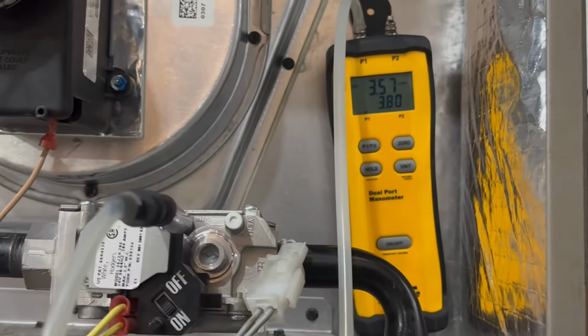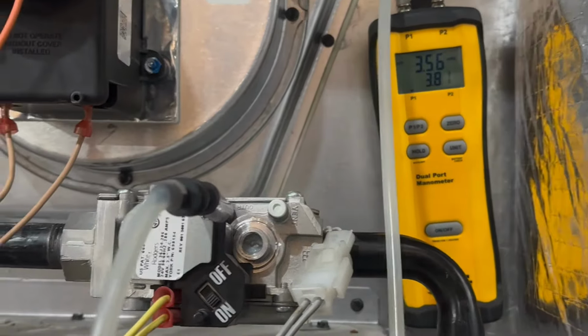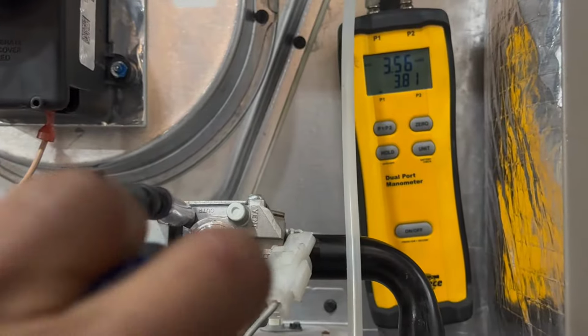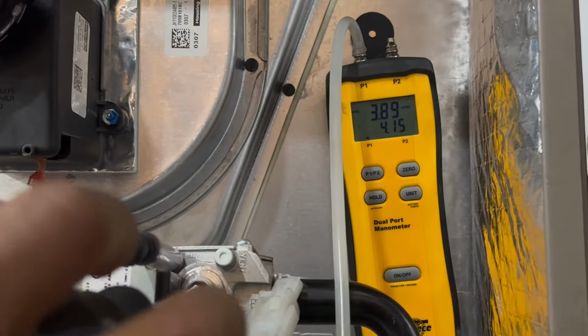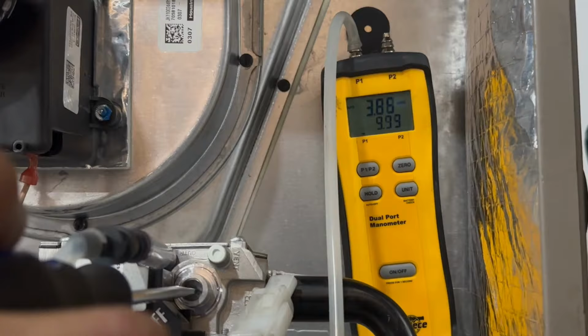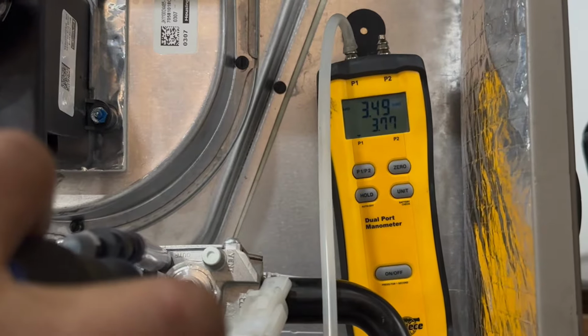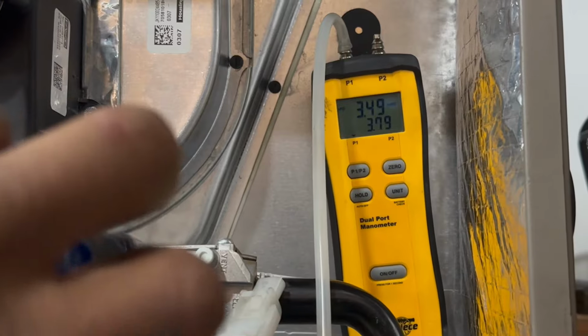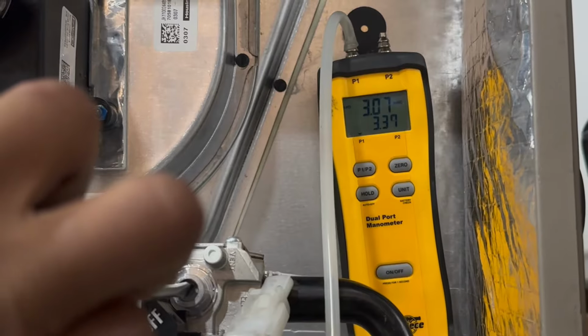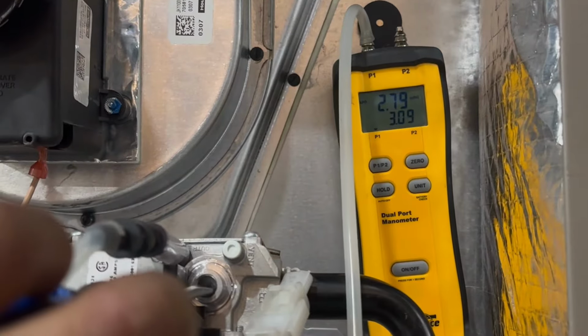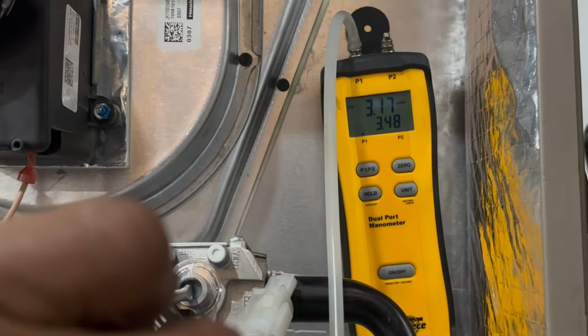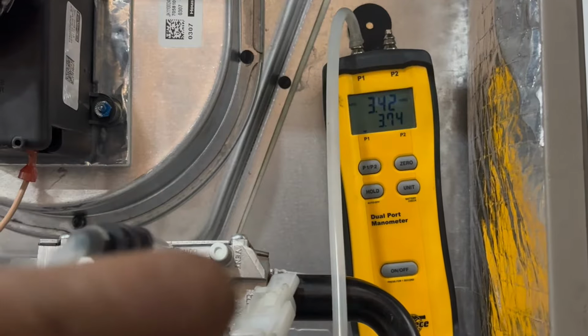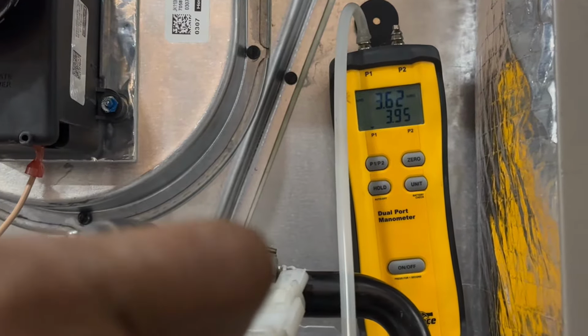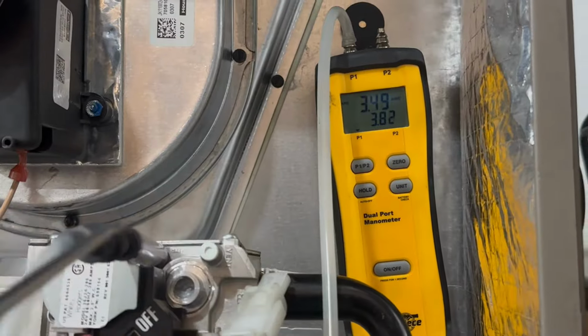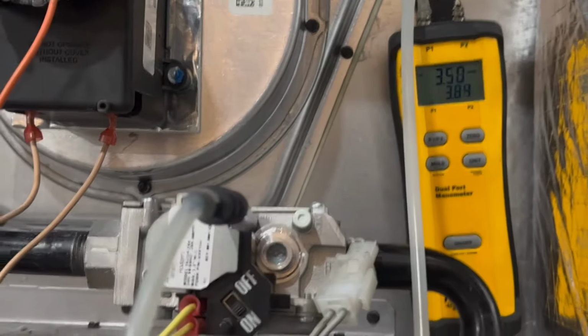But you're going to use a flathead. And look at my gas pressure there. To increase it, I'm going to go ahead and put my flathead in there. You see, as I go to the right, look at that. It went from 3.5 to 3.8. If I go to the left, I have less gas pressure coming out. You see, I'm spinning to the left. Now I'm at 2.8. But we want 3.5. So let's go ahead and increase it. That's good. We'll leave it there for now, just for you guys to see. 3.5. So that's how you adjust the gas pressure.